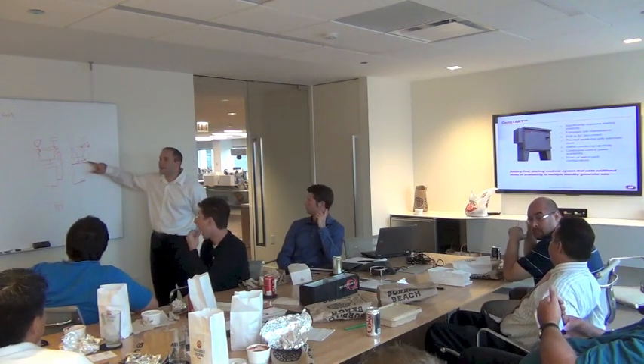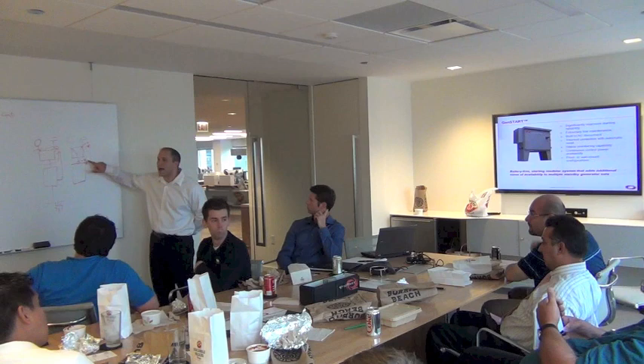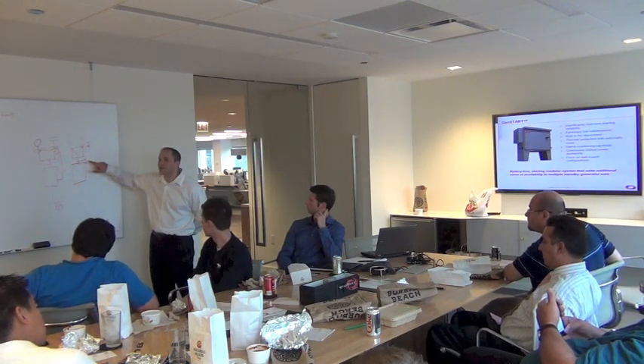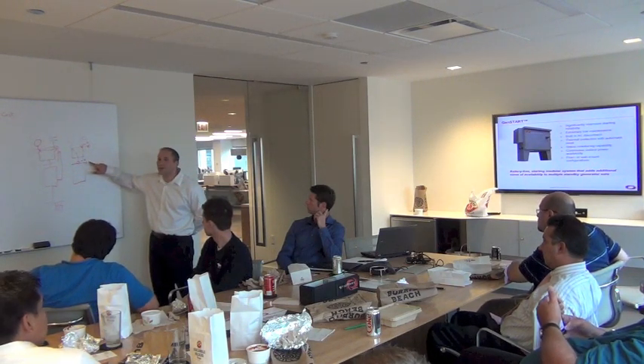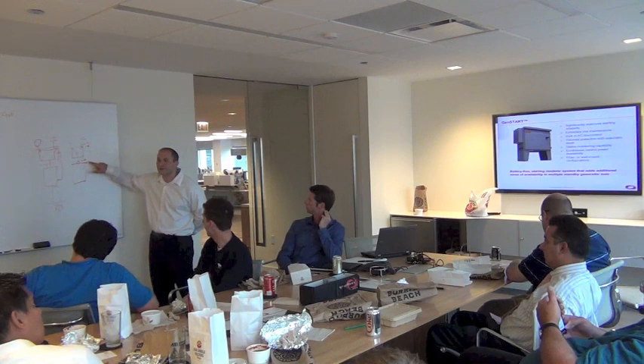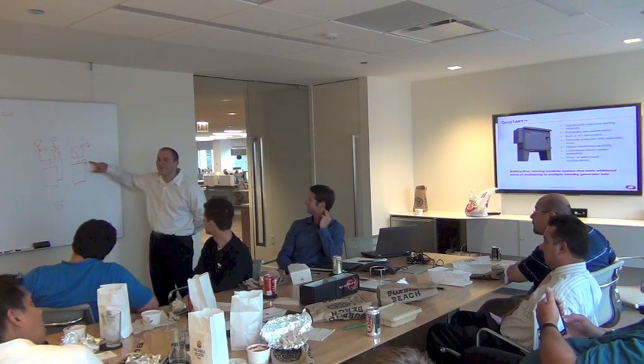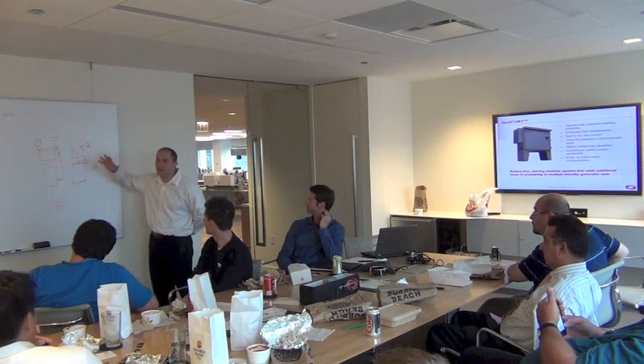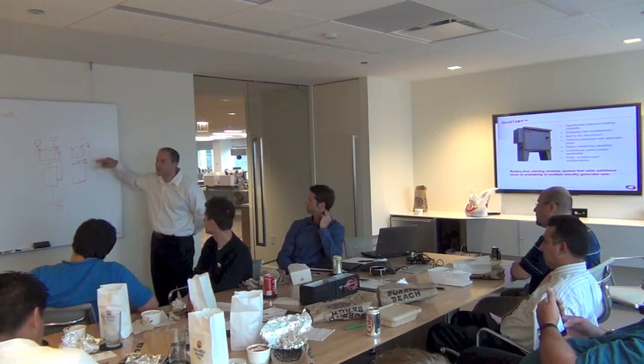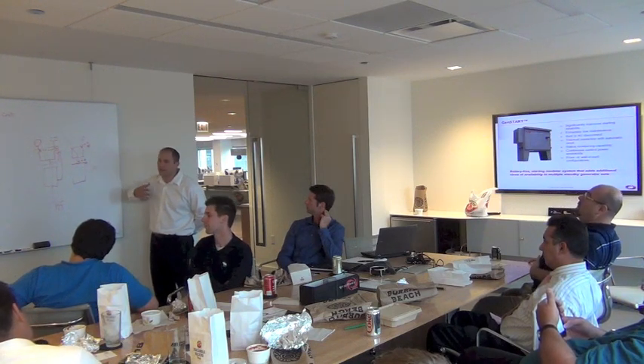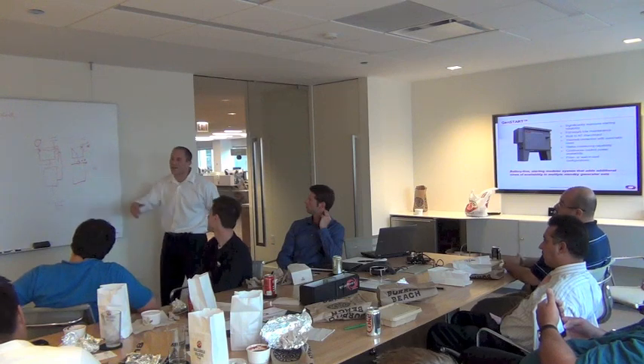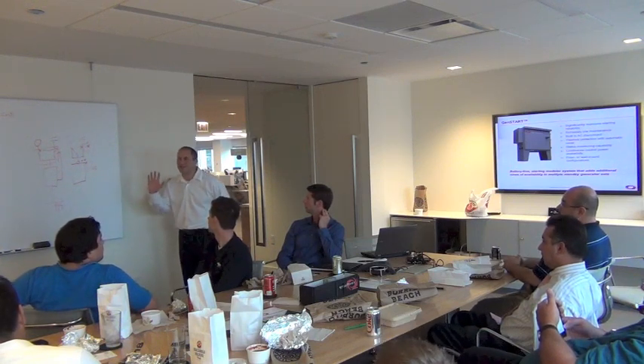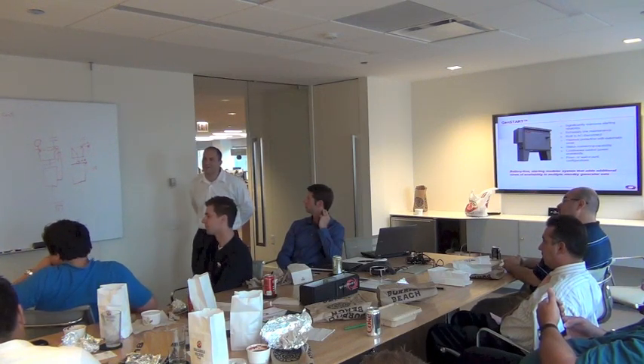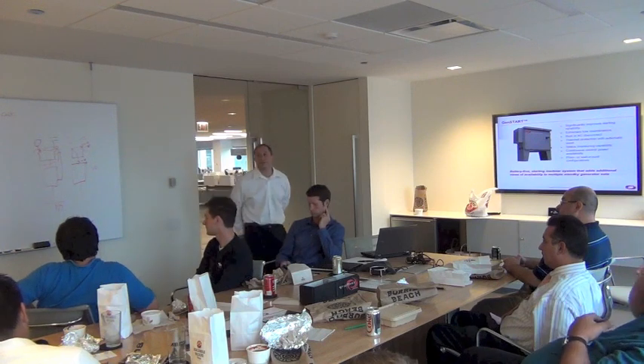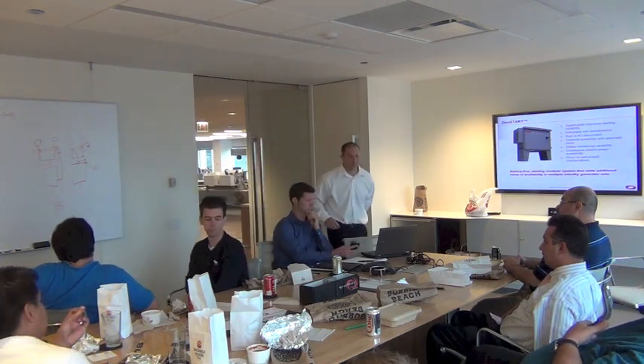I've seen a 10 megawatt site have no overvoltage detection on any of their transfer switches. They had half of our equipment on one side and half battery-based systems on the other side. And all the battery-based systems dropped the load, even though they had plenty of ride through time. They had an overvoltage situation that lasted a couple of hours. We had ATS command integrated in our feature. We operated perfectly on our side. The UPS had discharged for 7 to 10 minutes, and that was on the other side. And that was the end of it, by the time they found out what was going on. So it's a really nice feature, even for battery-based UPS.